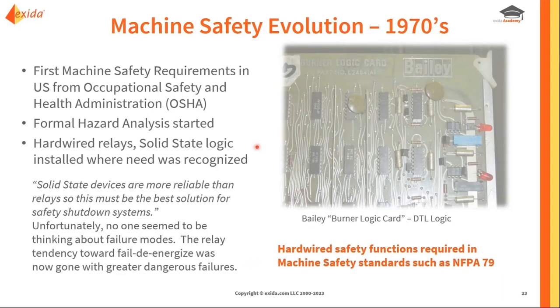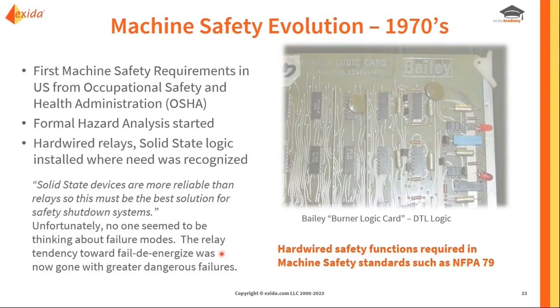In terms of the technology that was used, in addition to hardwired relays, solid state logic and other things started to be implemented and installed. People expected that because solid state devices were believed to be more reliable, using those solid state relays to shut down systems instead of hardwired relays was going to be safer. But what people found was there really wasn't a reduction in the amount of accidents, because when a hardwired relay fails, it tends to fail safe — it may have a higher overall failure rate, but most often it'll de-energize the system and prevent the dangerous state from occurring, whereas a solid state relay has a higher portion of failure modes that wouldn't de-energize.